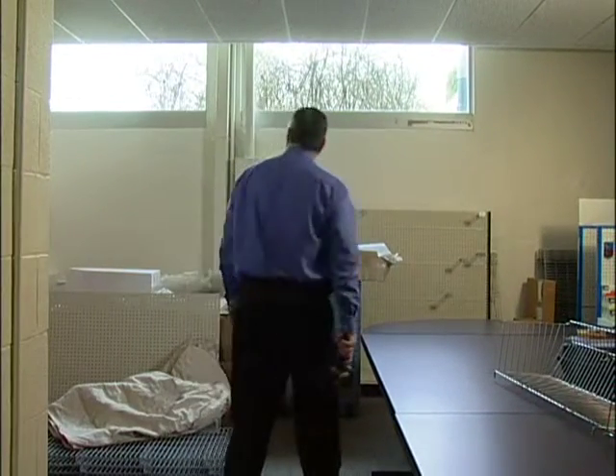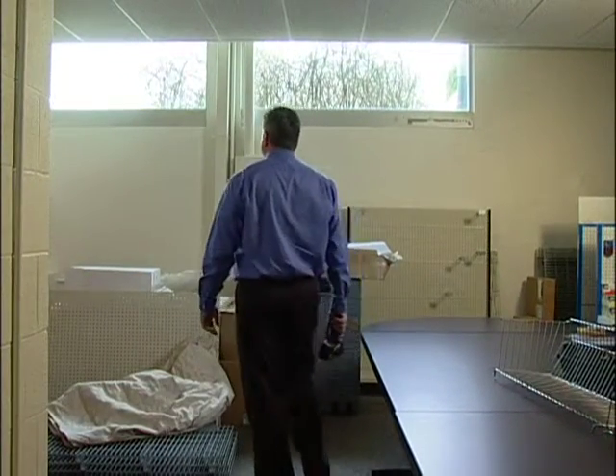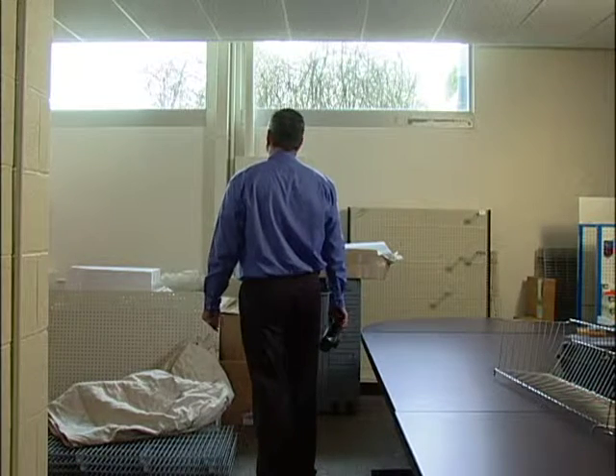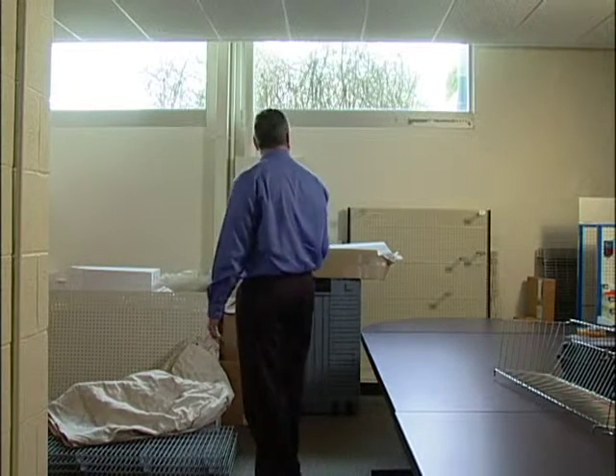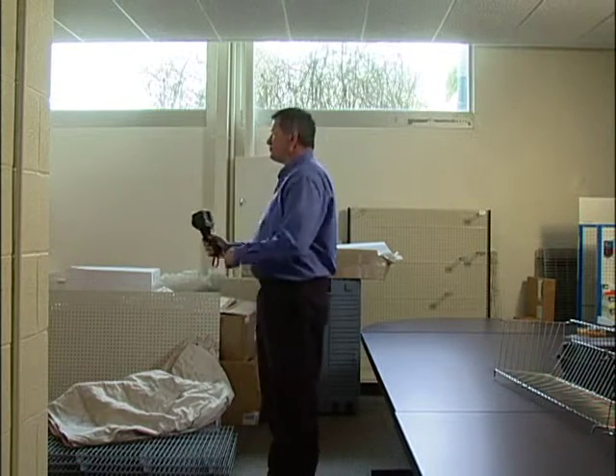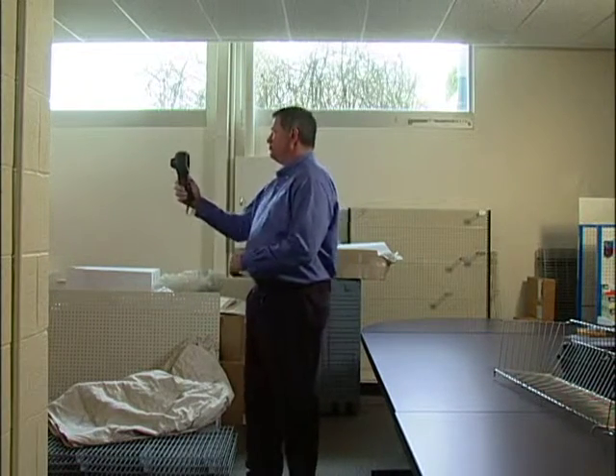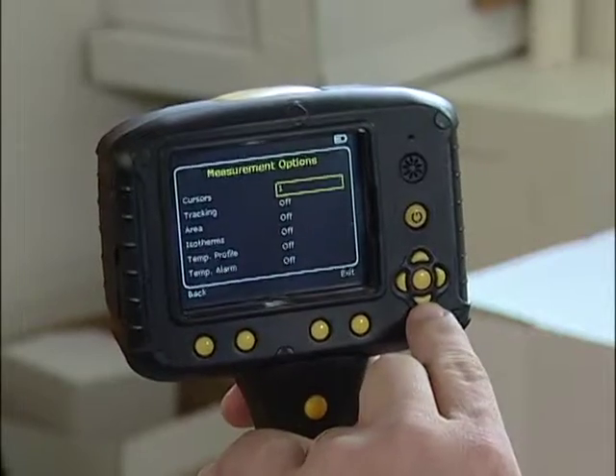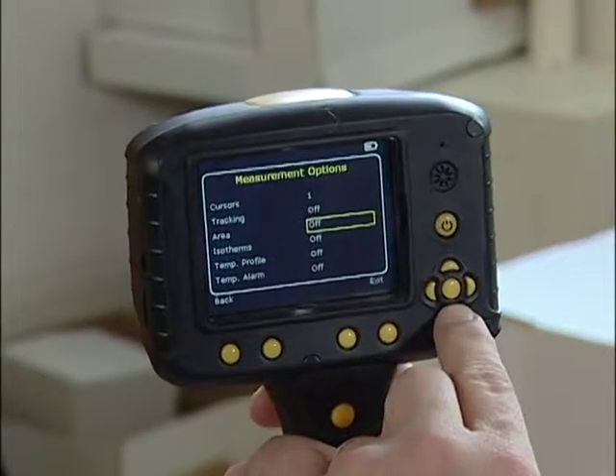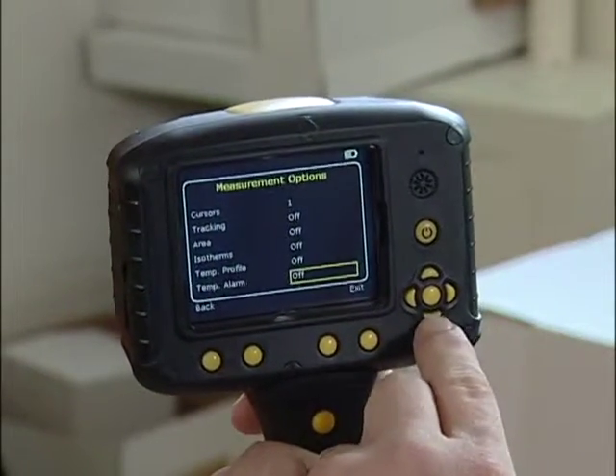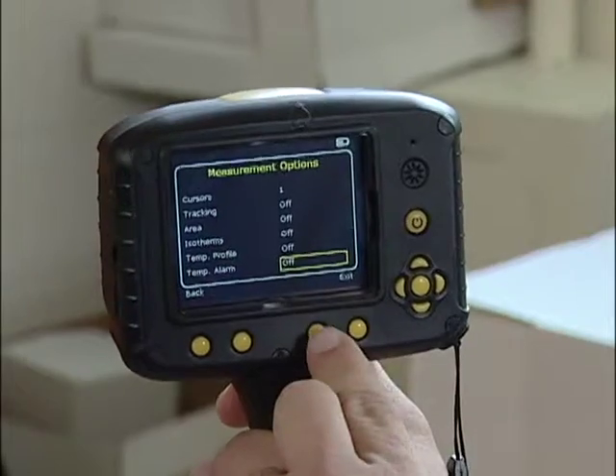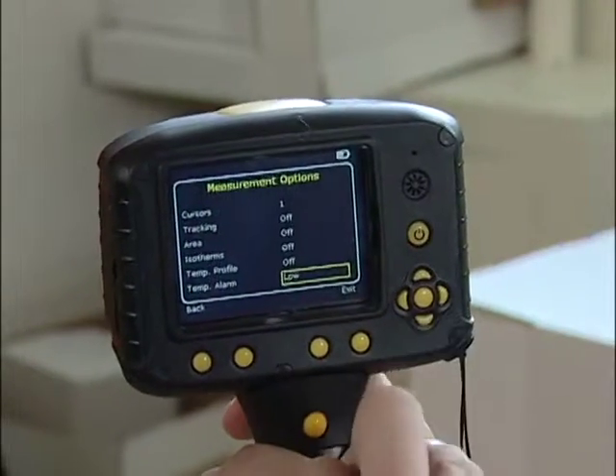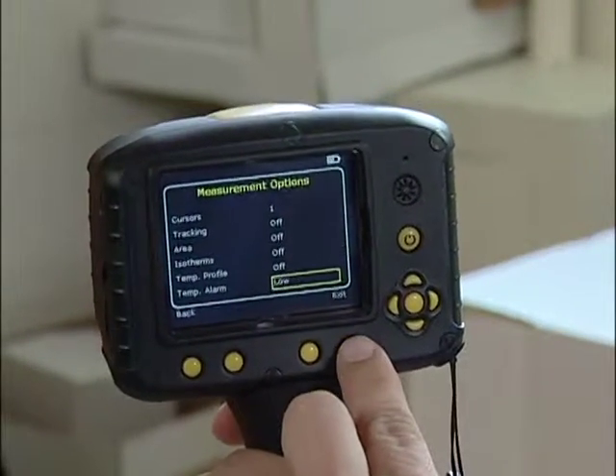In this example, the operator is checking the area around this window to determine if insulation is sufficient to prevent heat loss. First, determine the ambient room temperature. For this application, we'll use one fixed cursor, then set the imager to provide an alarm for a temperature below that amount.